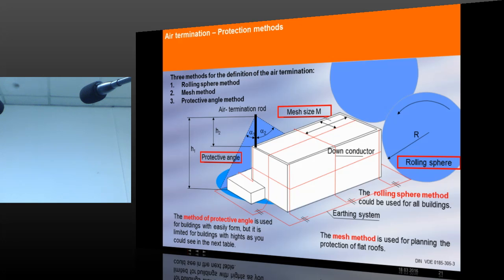These three are the normal methods of air termination, but more and more in the standard, a rolling sphere is explained. Rolling sphere means the energy equivalent of a lightning strike is electrogeometrically explained as a sphere. I don't know whether you understand. For simple calculation, you imagine 100 kiloamperes per lightning strike is equal to maybe this size of ball. And this sphere is rolled over the building, going from one side to the other. Wherever the ball touches, there is likely a chance of a direct lightning strike.